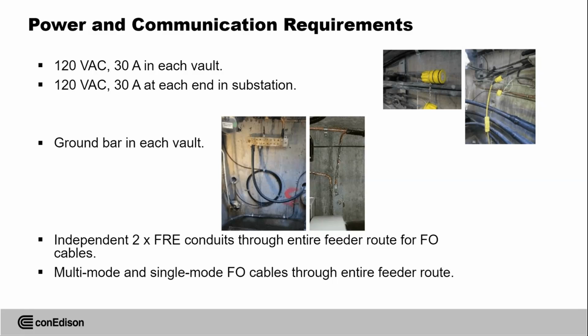We installed 2 fiberglass reinforced epoxy conduits for the entire feeder route for fiber optic cable. I know in the market many cable suppliers provide fiber optic as a replacement for one of the individual wires in the shielding. We are not in favor of that technique. We always request fiber in an independent duct. It's not a topic of this discussion, but we learned over many years the pluses and minuses, and decided to run fiber in a separate duct. So we use multi-mode and single-mode fiber optic cables for the entire feeder route. Multi-mode we use mostly for communication and data transfer, and single-mode we use for DTS and DAS for more precise measurements.